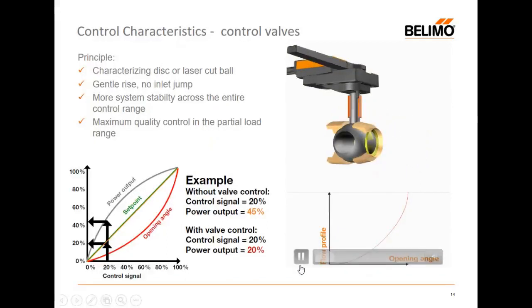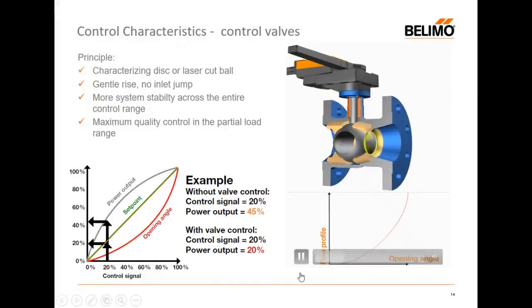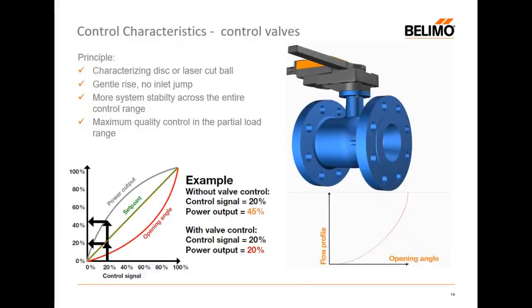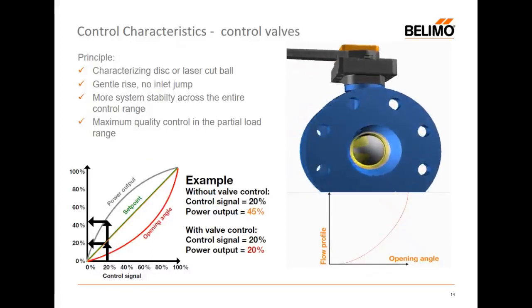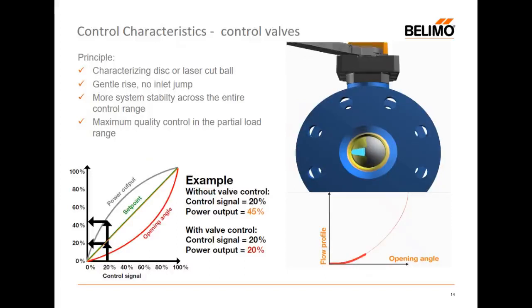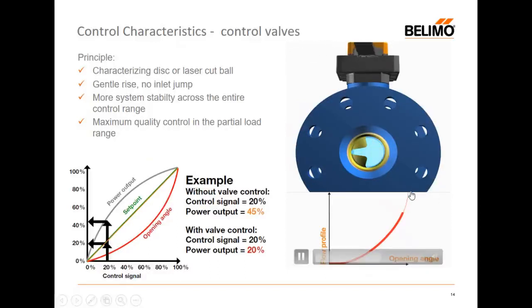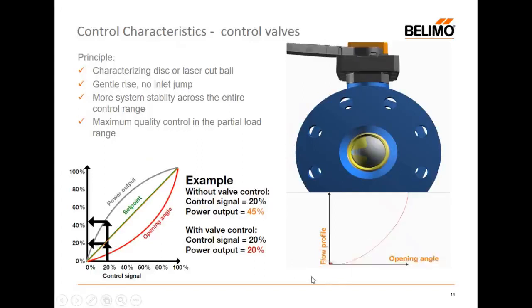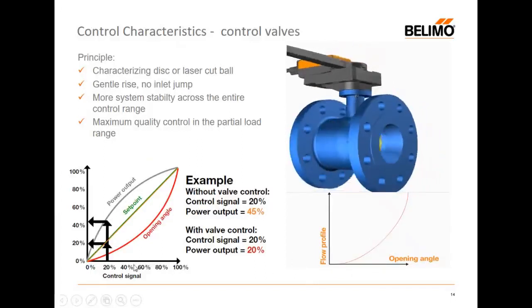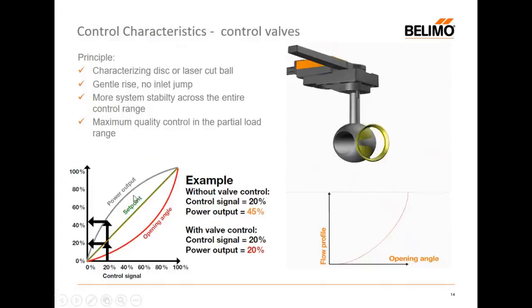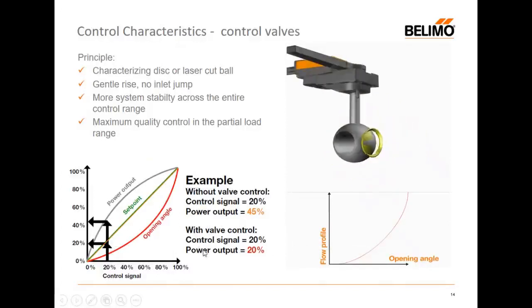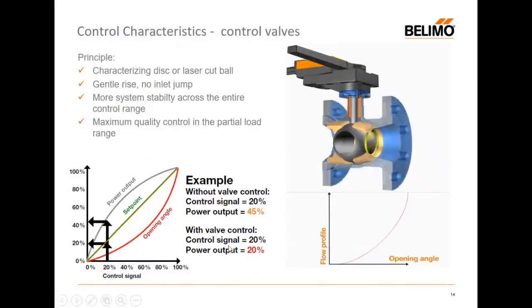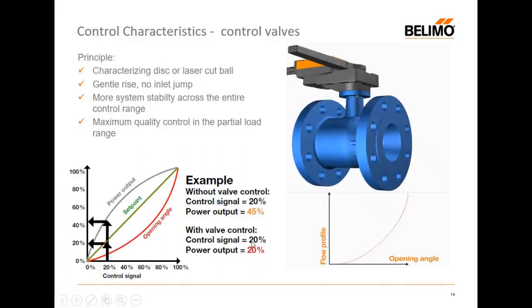And here's a little illustration of that. Here we've utilized a ball valve, which has now been characterized. There's a disc in there, which is affecting the flow path, such that the opening of the valve is nice and gradual, as you can see. And as the flow increases to fully open, we follow this nice EQM characteristic. And that's because the cooling coil has the mirror image opposite. And when we put the two together in the circuit, we want this ability, this compatibility, so that power output and control signal are proportional.